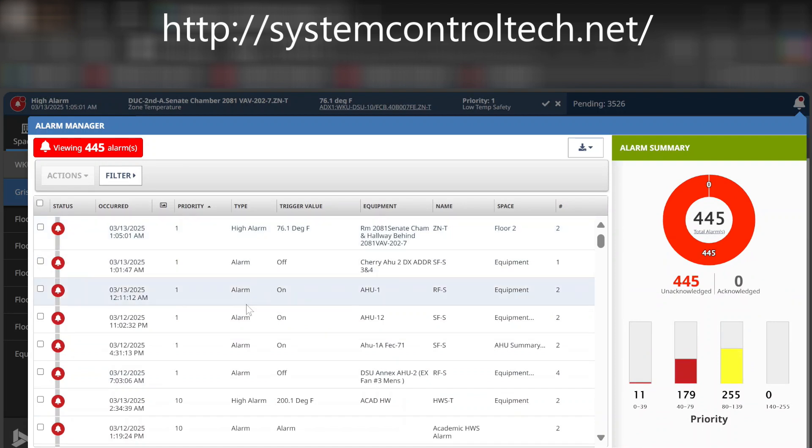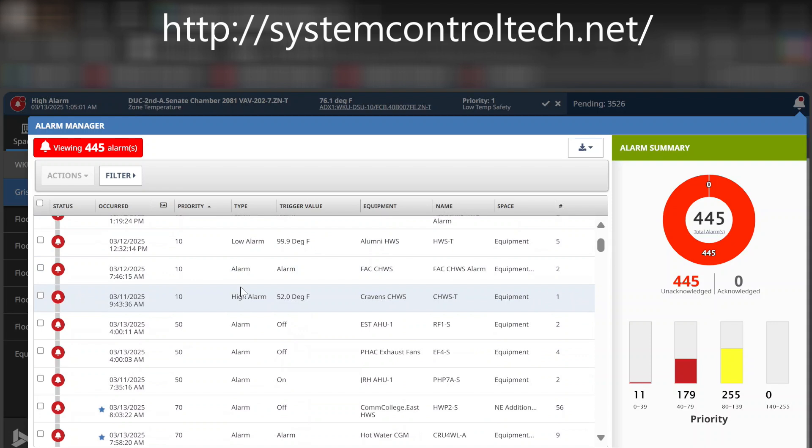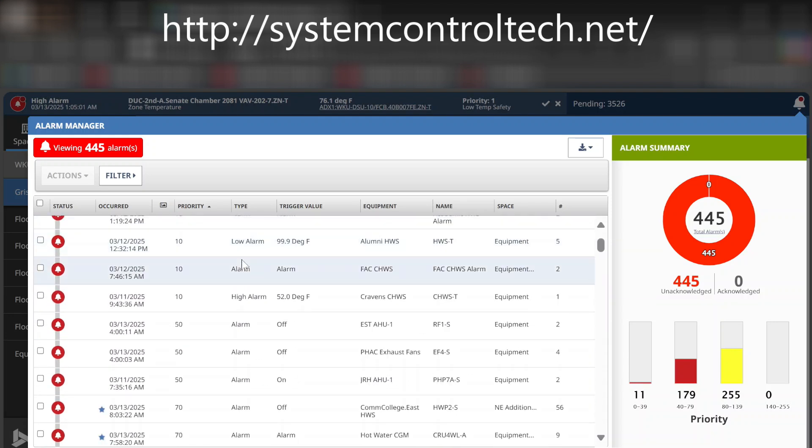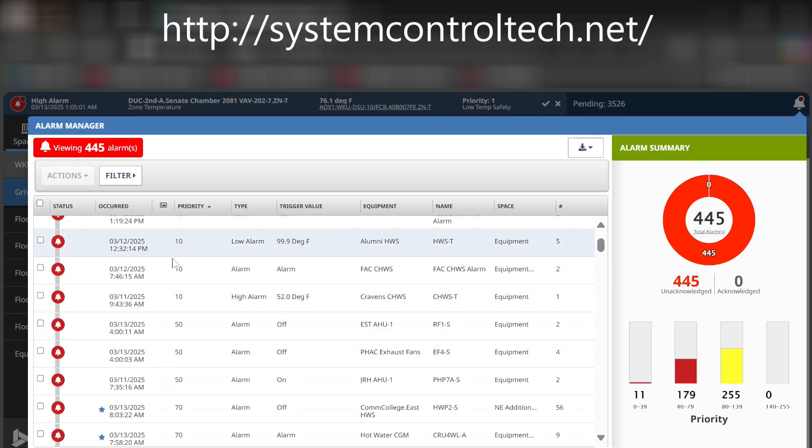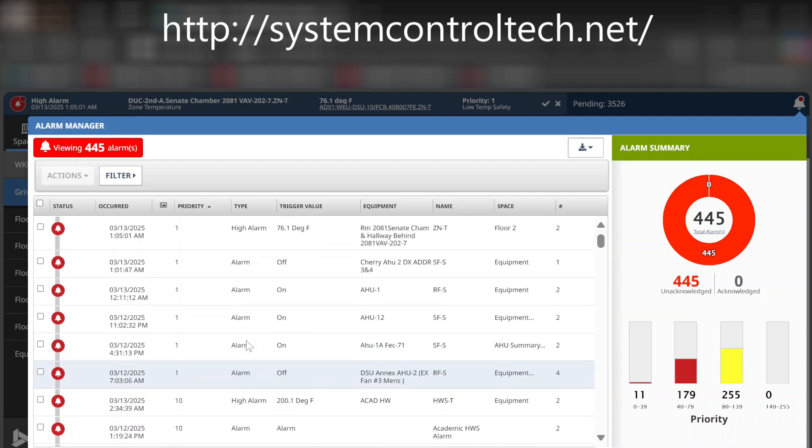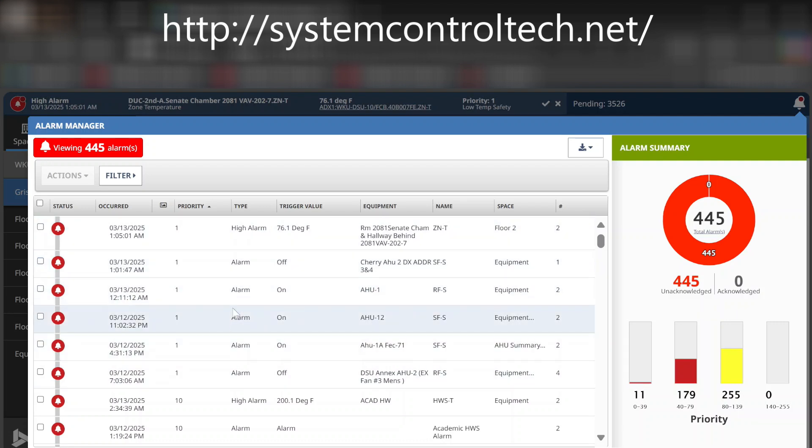Another way that you can use these is if you have, for example, multiple buildings on your system, and you have different technician groups that are within your organization, what you can actually do is sort them based upon an alarm priority, and you can assign a different priority category. Like, you can do all increments of 10 for one group, 20 for another group. It really depends on what you want to do within your organization. For us, that's one of the first things that we want to know is, are there any alarms that need someone to physically go and reset that system?